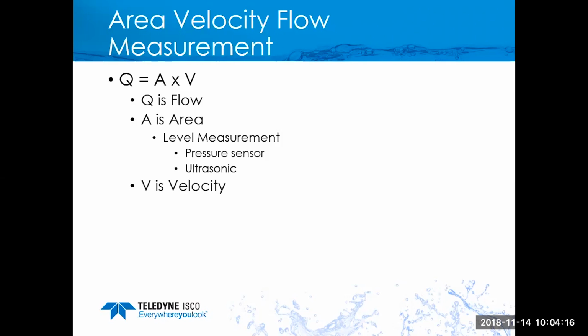V is the velocity component. The most common way of measuring velocity is using Doppler or a Doppler shift. There are either contact sensors, and by contact I'm referring to one that's on a band that's in the pipe. Non-contact would be just as it implies, not in the flow, and that would be what the laser will do.